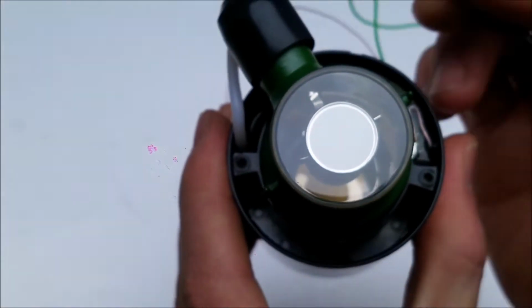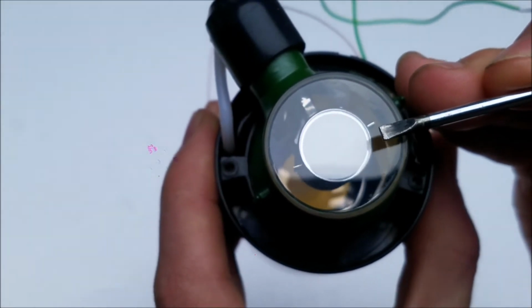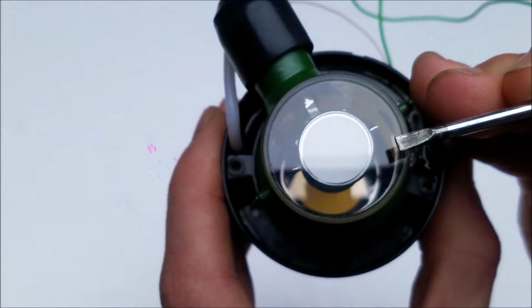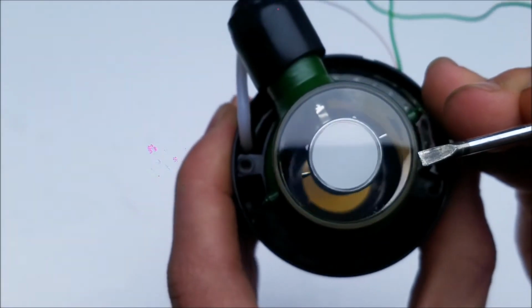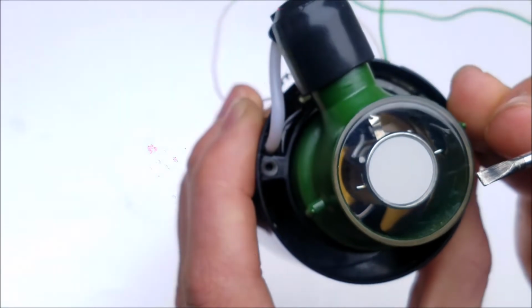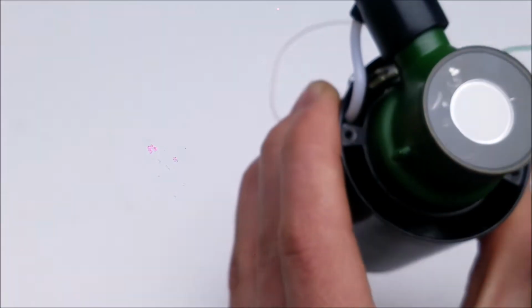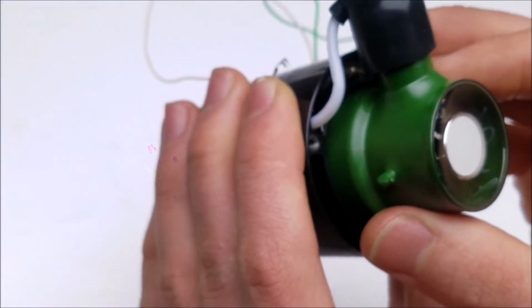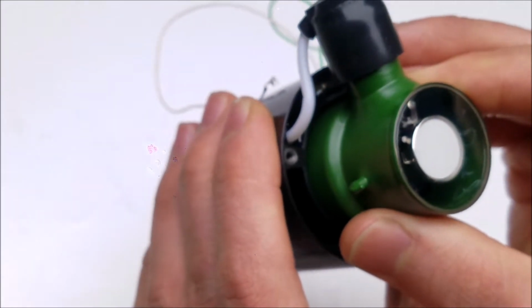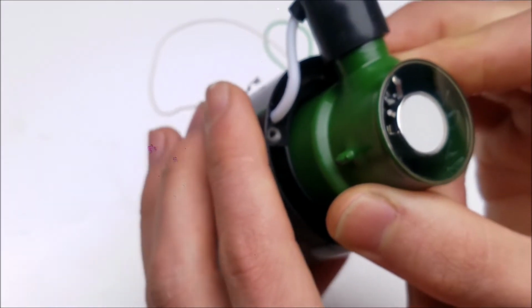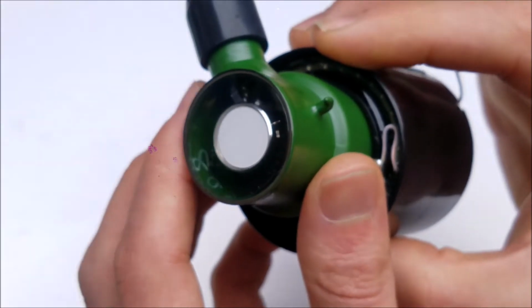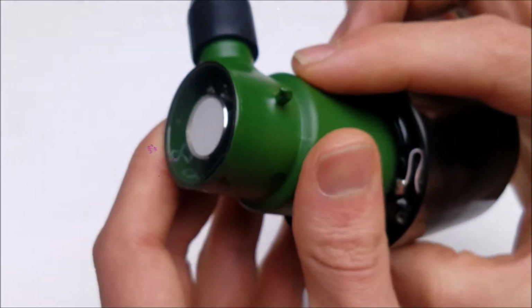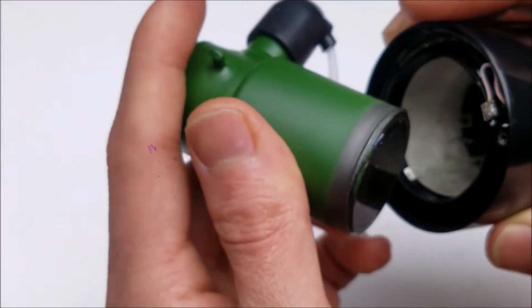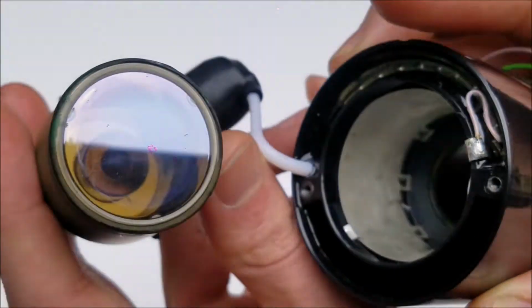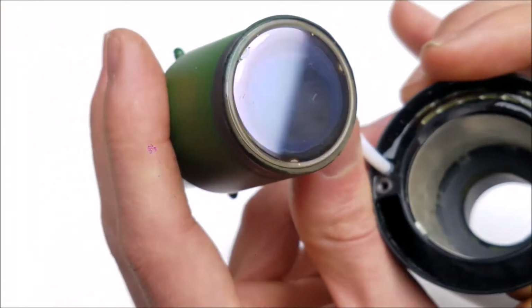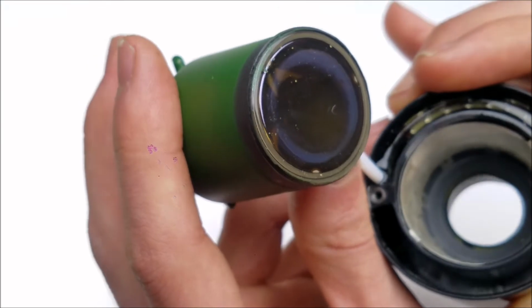And then we have the phosphor screen. So green phosphor screen, just like you see in a CRT tube. It's a monocolor. Let's see if we can pull this out. Oh yeah, it is pretty loose. Okay, that's good. Oh yeah, that gives us a better view, and I can clean the photocathode. That looks pretty dirty.